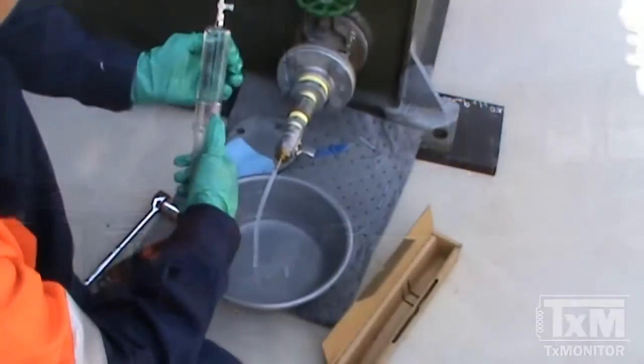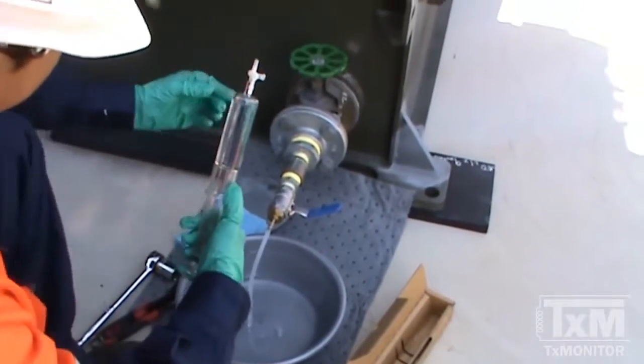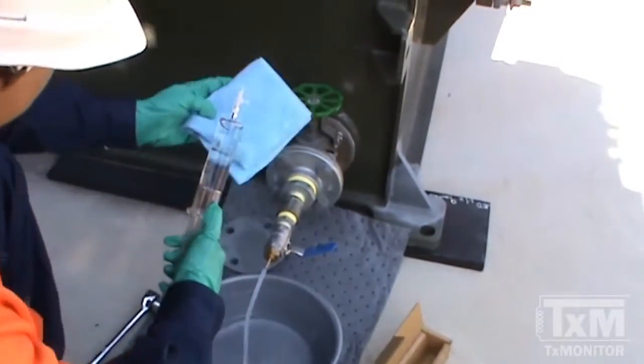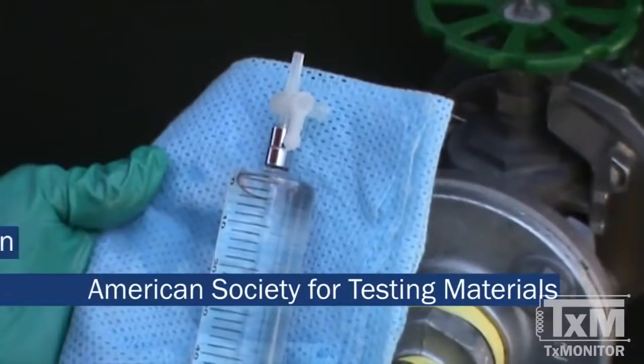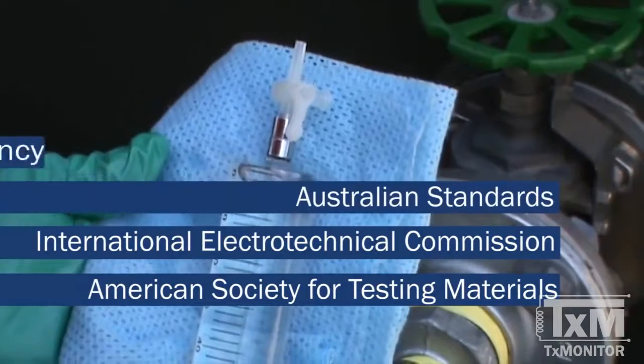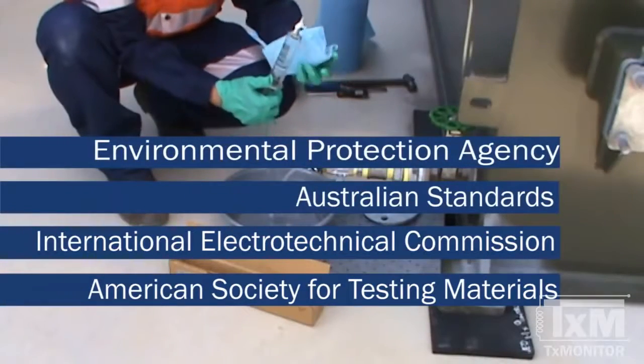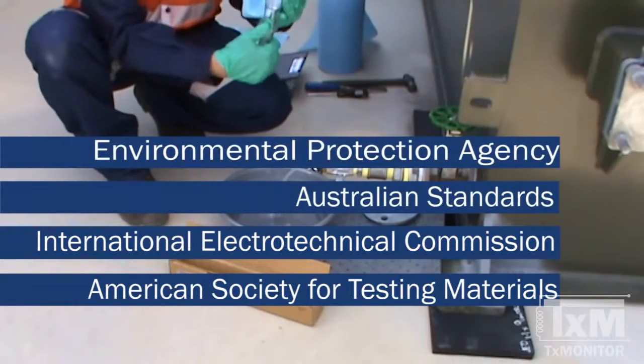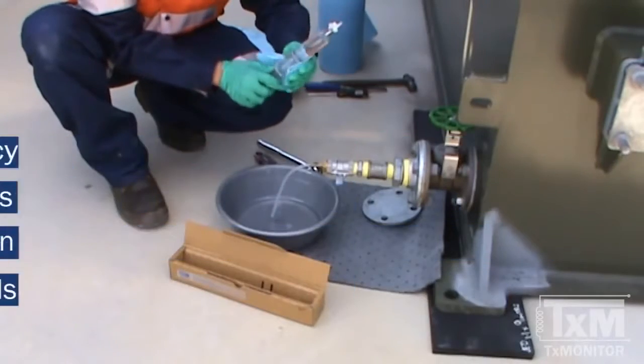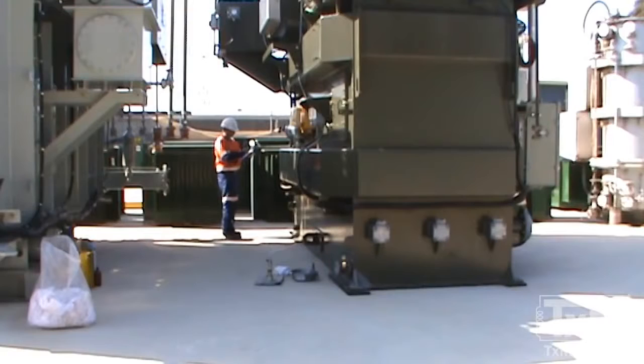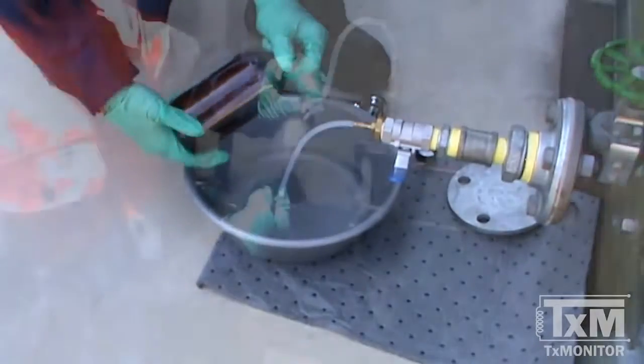The techniques shown here follow the guidelines of internationally recognised standards such as ASTM, IEC, AS and EPA. The modules in this sequence demonstrate the specific techniques required to perform oil sampling from the bottom valve of a power transformer, as well as oil and gas samples from the sampling port attached to the Buchholz gas accumulation relay.